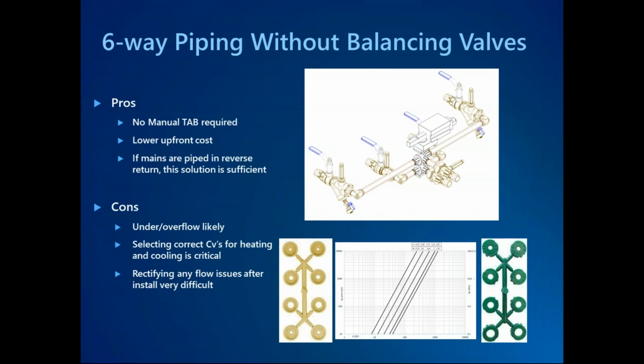Times when this can be applicable and can be a successful design is if you're doing reverse return piping on all of the mains. So every single six-way is going to see relatively equal pressure drops to its neighbors and the rest of the building. In that sense, you can get away with just using the CV discs. But underflow and overflow is still going to be likely if we're not designing the reverse return piping perfectly, and trying to rectify any flow issues down the road without some type of balancing valve is going to be very, very difficult. So quick and dirty, what we call poor man's balancing, is doable with these CV discs, but it's definitely not the recommended way to do it.